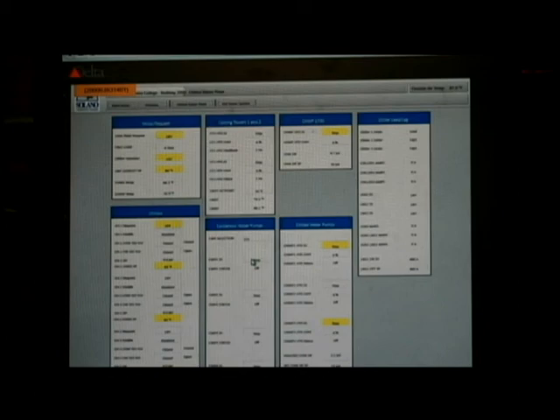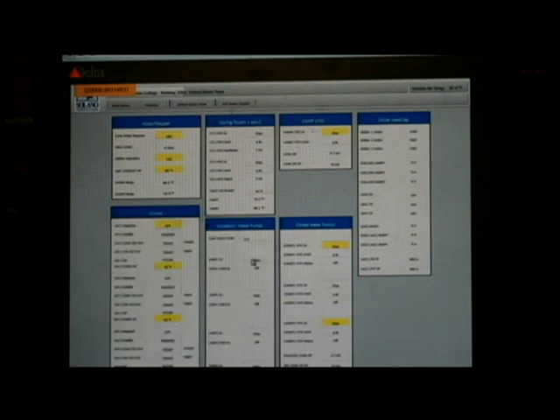As demand in the loop increases and more chilled water is needed, or more capacity to maintain the chilled water set point, then chiller number 3 will come on. And the very worst case, which I don't believe has ever happened before, is chiller number 2 as a last resort, where you have all 3 of them running. On these systems, we always start with the large chiller, so your lead is always going to be 1 or 2. Your number there is always going to start with a 1 or 2, and then 3 comes in as lag 1, or whichever one is lag 1 and lag 2.